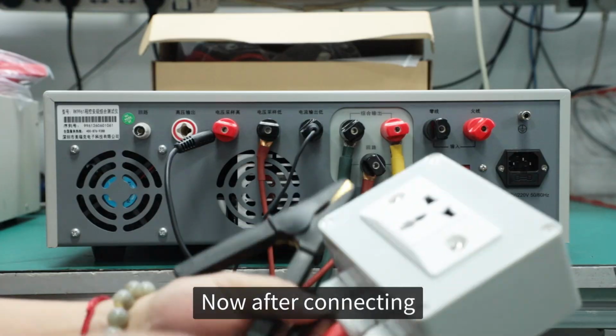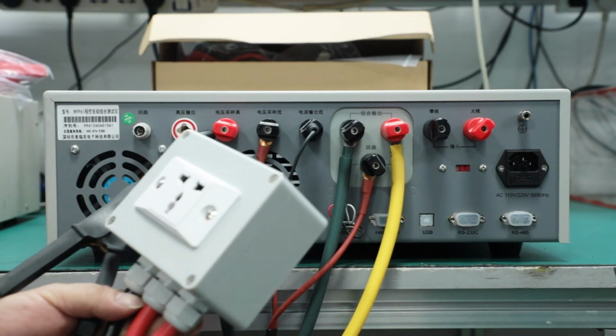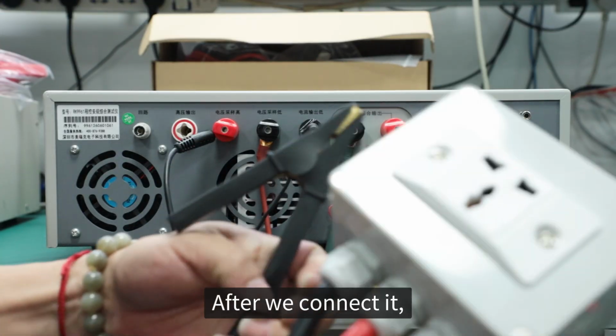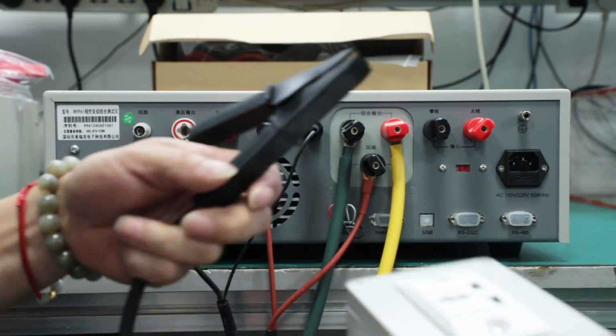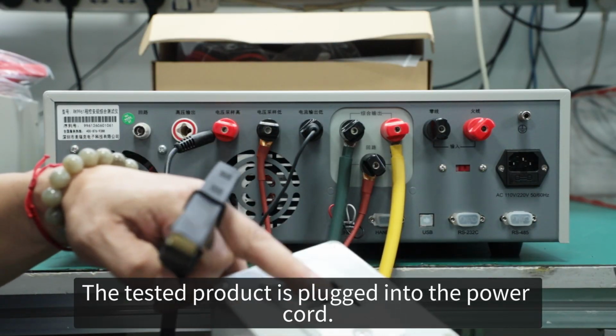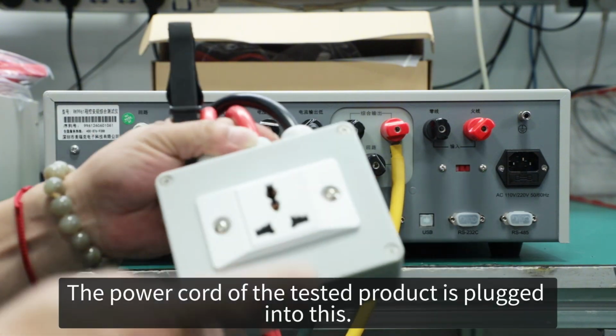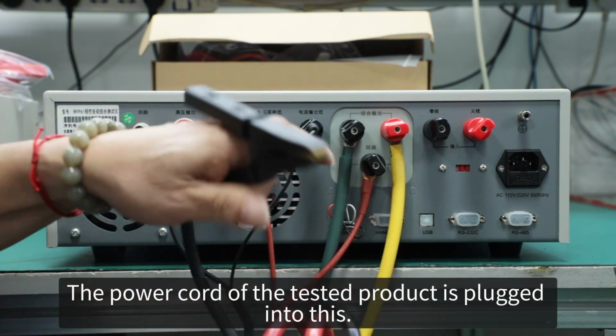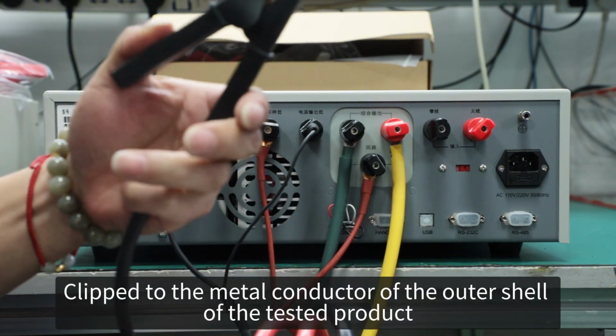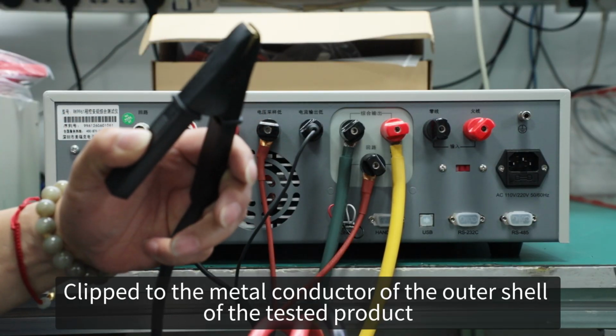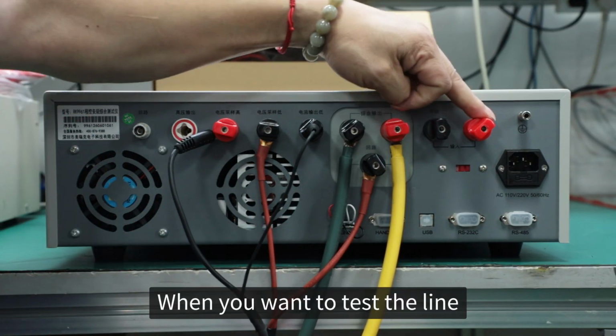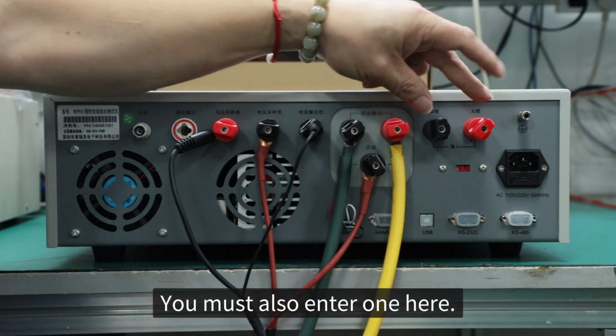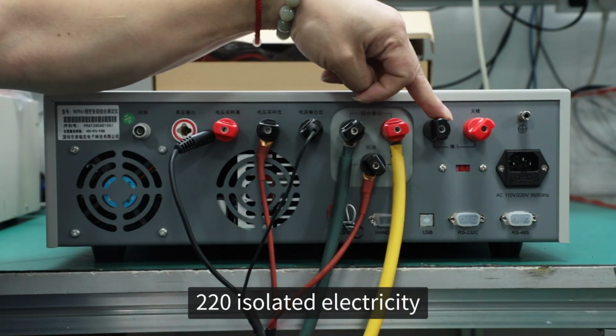Now after connecting, this comprehensive box: the power cord of the tested product is plugged into this box. This big clip clips to the metal conductor of the outer shell of the tested product. When you want to test the line, you must also feed one in here, 220 isolated electricity, coming in.